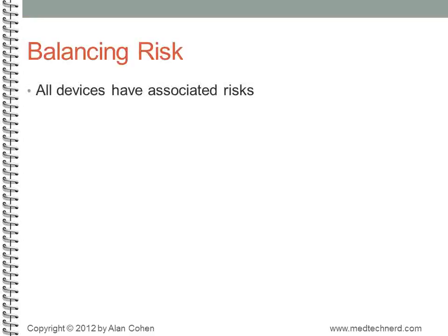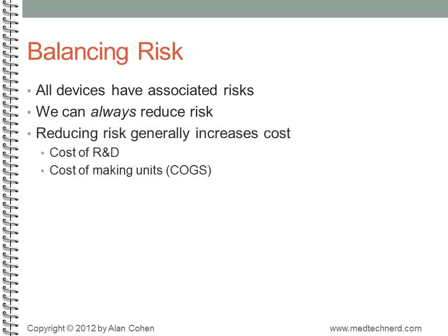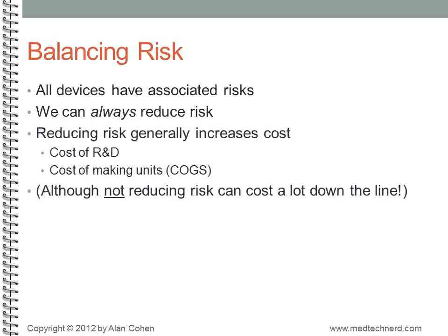All devices have risks associated with them, and we can always reduce risk. We can always make a device a little safer, a little better. But that generally means we spend more money and take more time on R&D, and it often means increasing the manufactured cost of a device as well. On the other hand, if something bad happens because we didn't reduce a risk, and say people get hurt unnecessarily, not reducing that risk could turn out to be much more expensive than reducing the risk would have been.